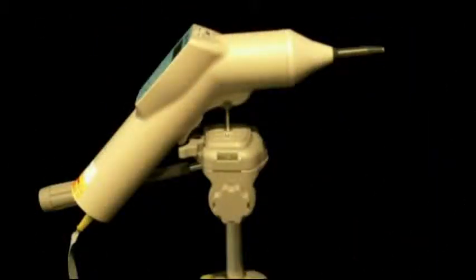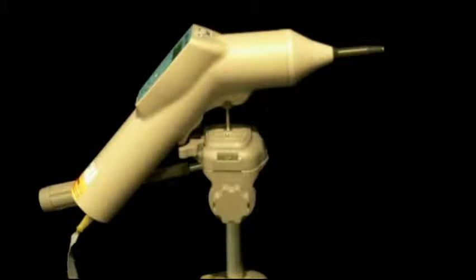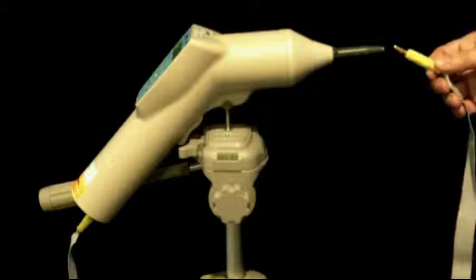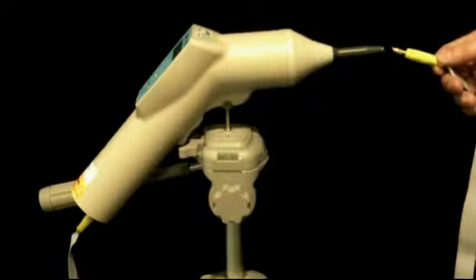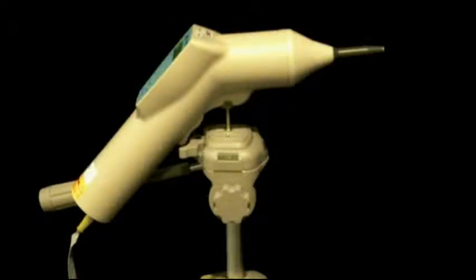To do an air discharge demo, place the gun in air discharge at 16KV for multiple repetitions. Once that's programmed in, hit the run button, the LED will start flashing. Then hit the trigger, the ESD gun will charge and be ready. Make sure to have your ground cable connected to the bottom of the ESD gun and then slowly go towards the tip of the air discharge tip. You will see spark. Always make sure to go slowly in towards it. That concludes our demonstration of the ESD3000.